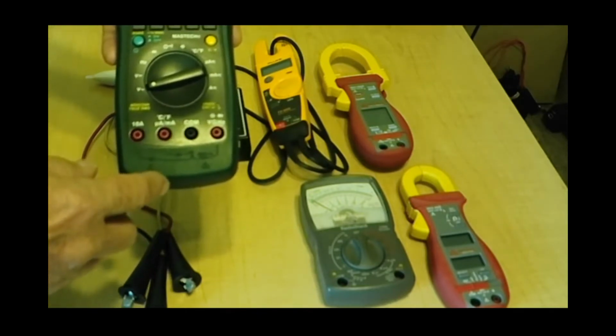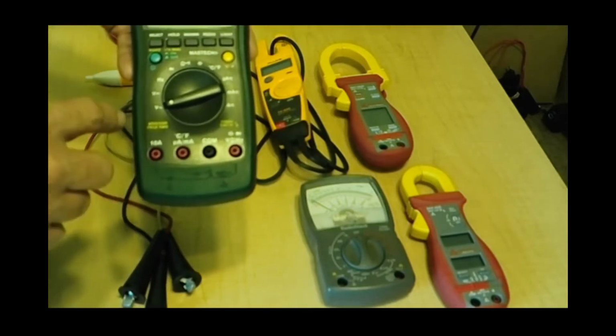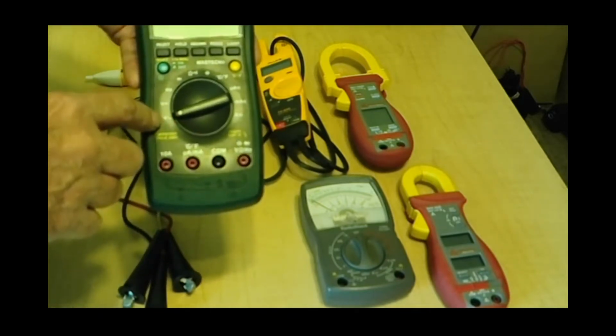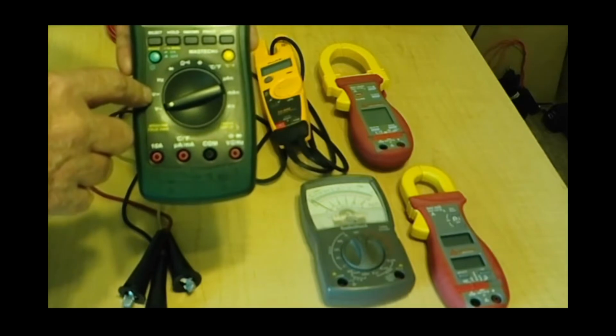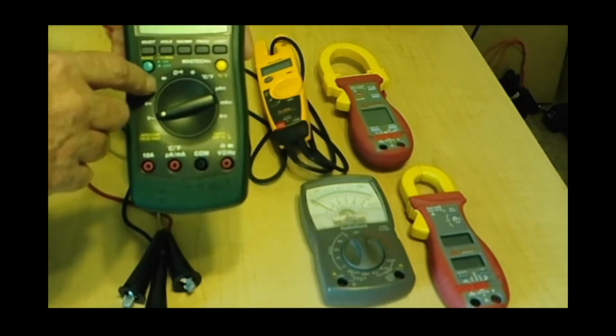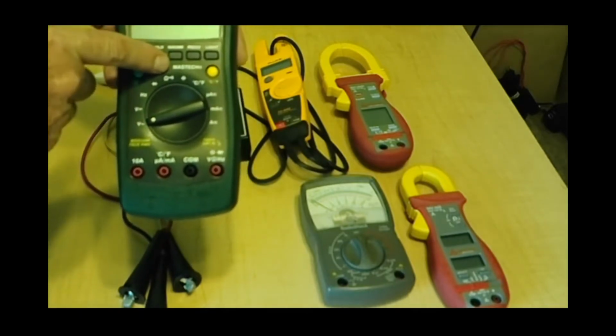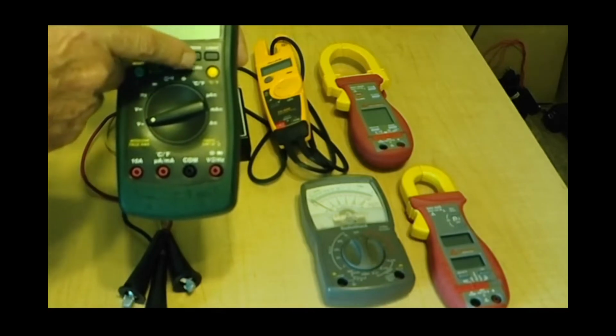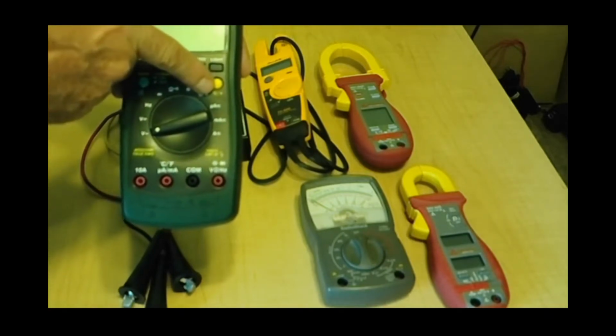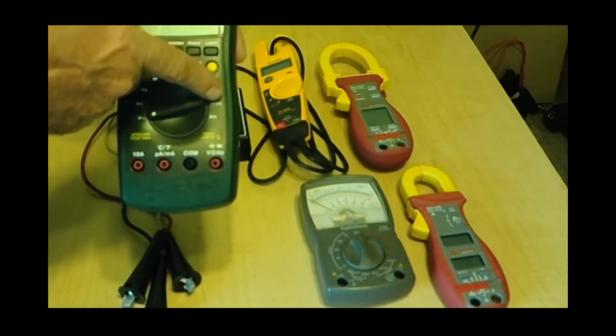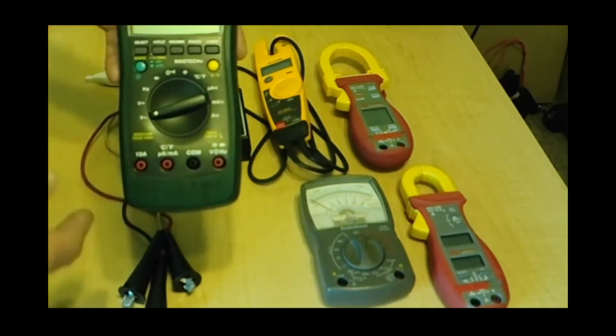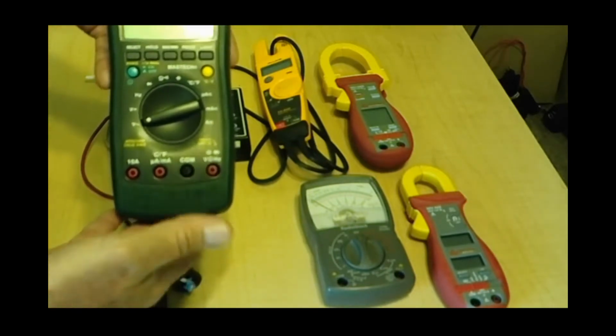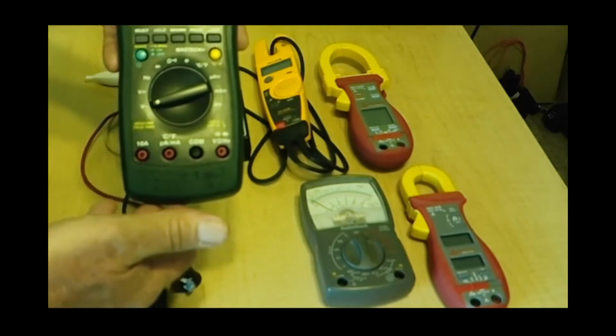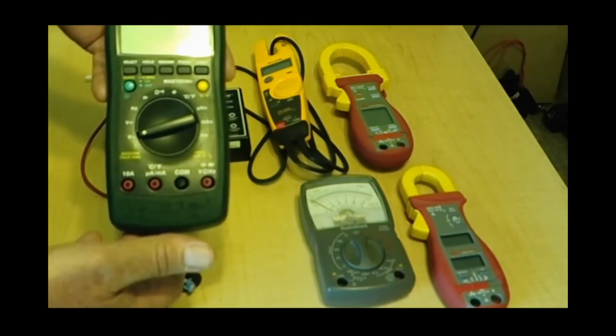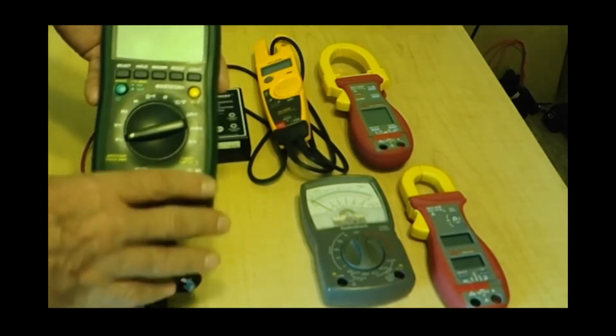So they're very specialized. Now this specific meter right there will read a lot. You have AC voltage, DC voltage, frequency, reads diodes, ohms, continuity, capacitance, temperature, microamps, milliamps, and amps. Very useful type of meter, but this meter, because of its functions, is more often used right there on a test bench rather than in the field.